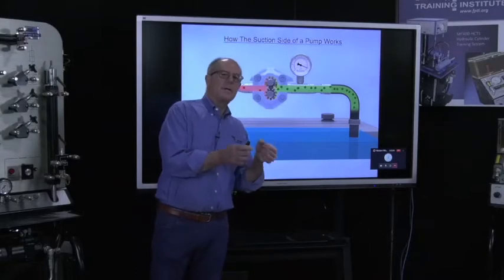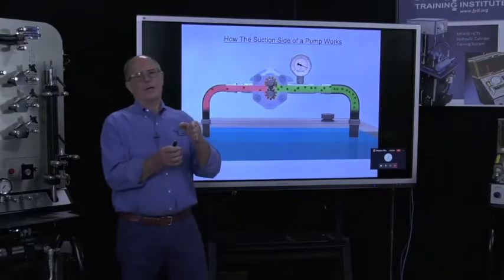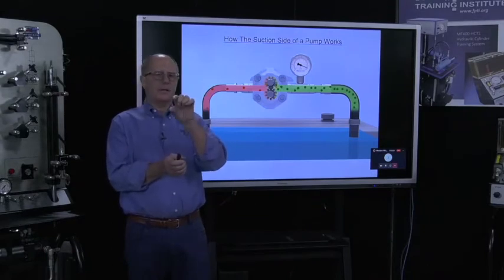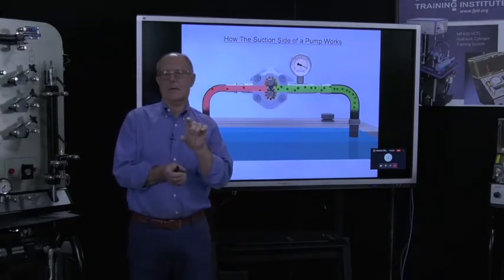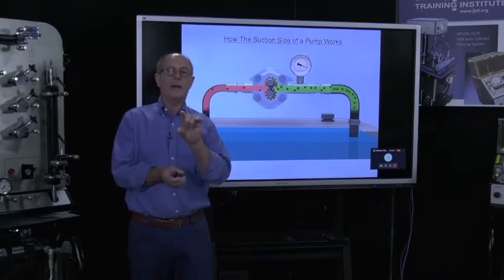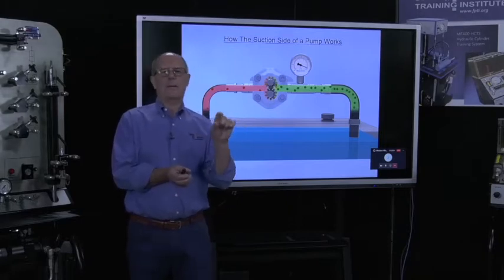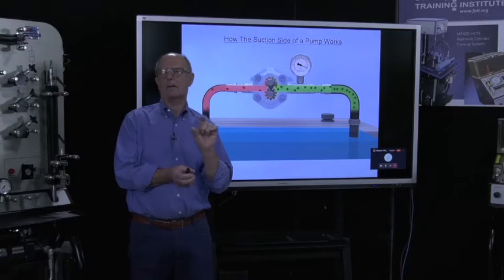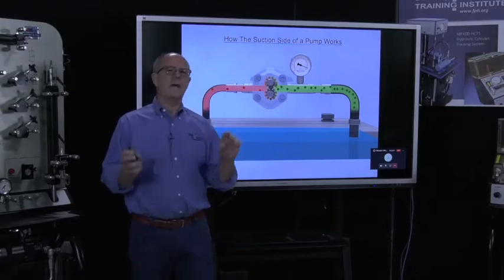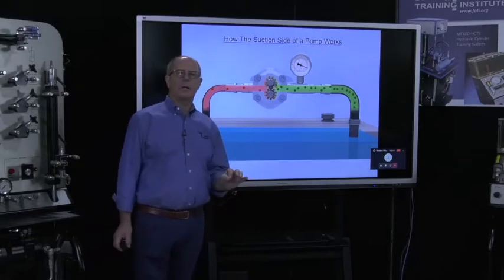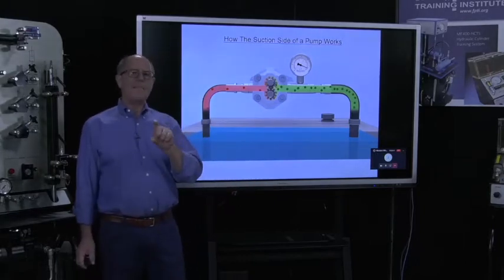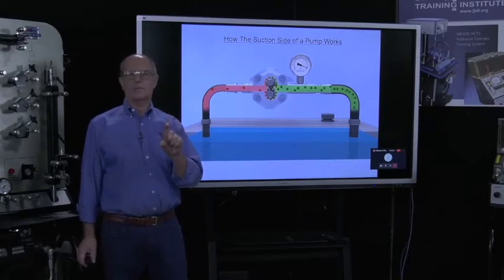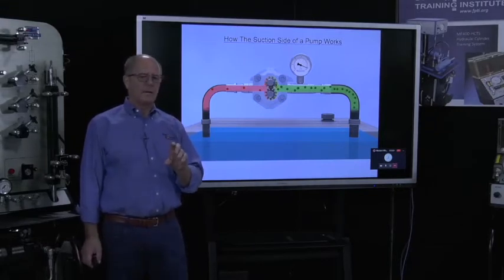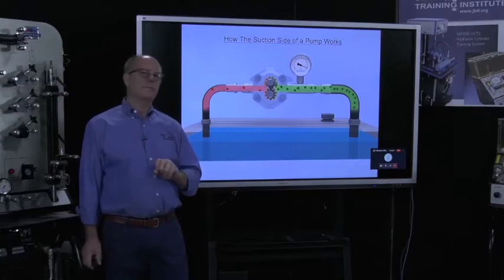The manufacturer of the pump tells the machine manufacturer's engineer that when they start the pump, they should go to the assembly line or down onto the prototype unit, and make sure that the inlet restriction is well within the maximum inlet restriction recommended by the respective pump manufacturer. So let's give that a number. Let's say this is a gear pump on the screen. By rule of thumb, the maximum inlet restriction at normal operating temperature, which is about 135 degrees Fahrenheit, is 8 inches of mercury. It can cold start to 10, but it cannot exceed 8.